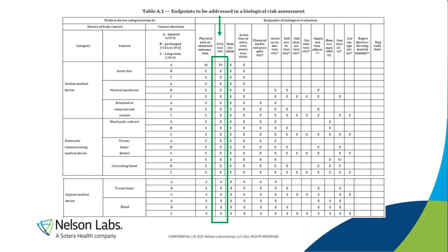And since the cytotoxicity test is a fairly quick, simple, and inexpensive test in the realm of all the biocompatibility testing out there, it is often the one that is actually performed, rather than using a rationale or justification for not doing it. Also, it is often used as an initial screening test to see if there's anything concerning present in the device extract. So that's why we have to do it.